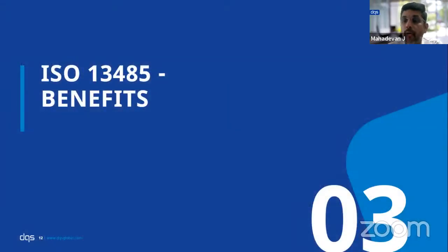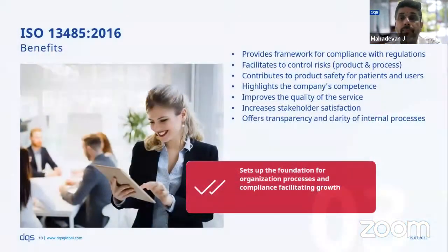Having seen the interlink between the regulations and the 13485 requirements, let us see the benefits of compliance with 13485. It provides the framework for compliance to the regulatory requirements. We have seen that in detail now. And it facilitates control of your risk with respect to your product as well as your process. How it facilitates is that there are requirements in the standard which ask you to review your changes, and whenever you do any change, you need to revisit your risk management to see how it is impacting, in terms of further reducing the risk, your product or even your processes.